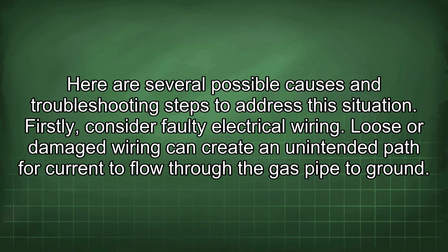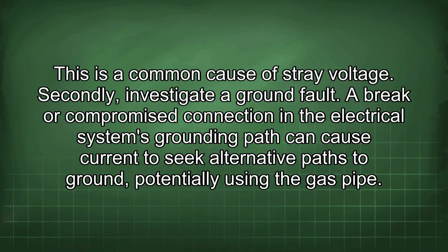Firstly, consider faulty electrical wiring. Loose or damaged wiring can create an unintended path for current to flow through the gas pipe to ground. This is a common cause of stray voltage. Secondly, investigate a ground fault. A break or compromised connection in the electrical system's grounding path can cause current to seek alternative paths to ground, potentially using the gas pipe.